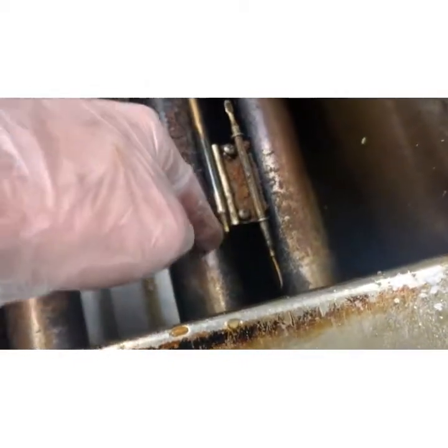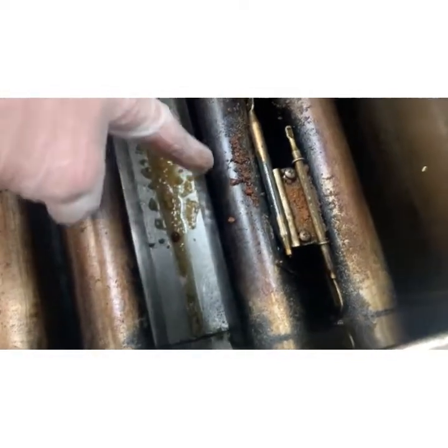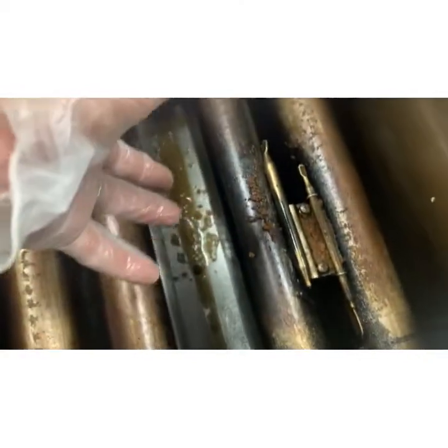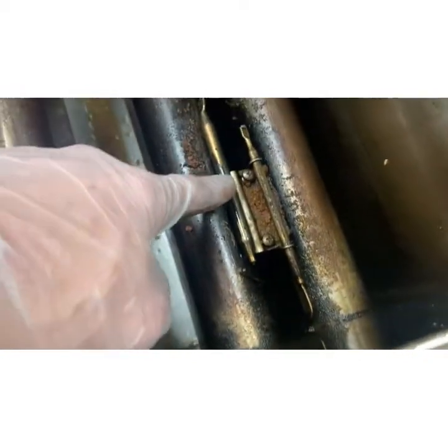Boom - so there's why the high limit broke, or why the thermostat broke. It was sitting way too close and in contact with this tube. These tubes run 700 degrees and transfer the heat out to the oil. The probe needed to be under that bracket. It came out.